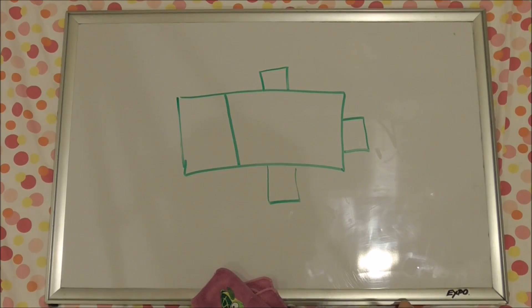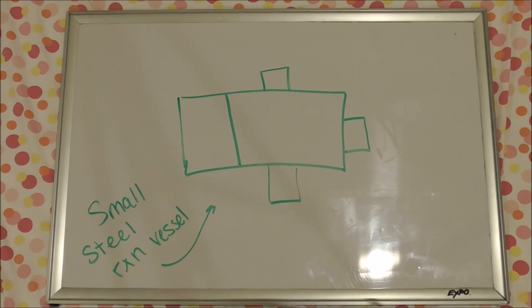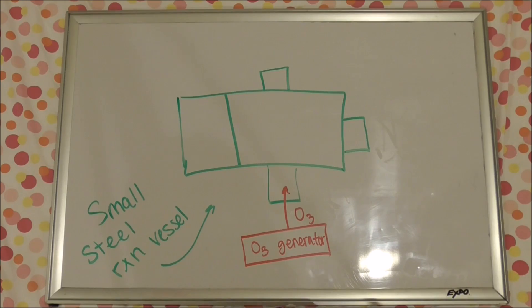In order to determine the concentration of NOx, it has to be conducted in a small steel reaction vessel. And so what that vessel does is that it has a small ozone generator attached to it and it'll feed ozone into the vessel.